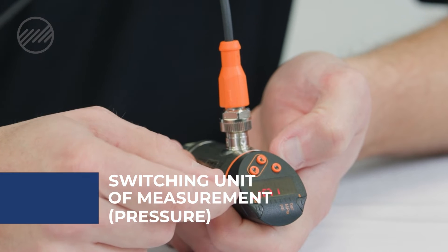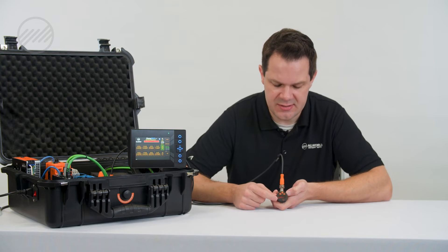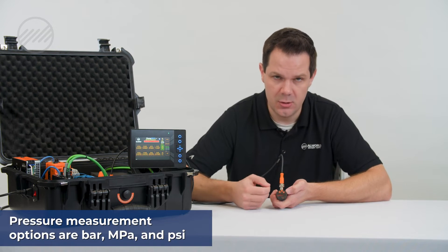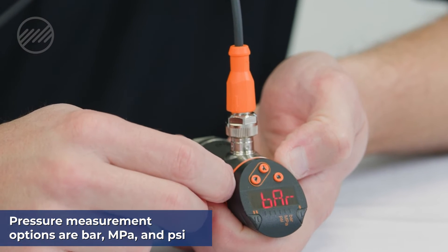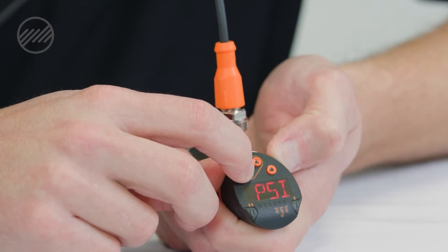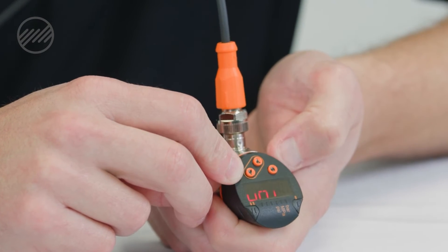Also in this section we have our units of measure. Typically these come out of the box as bar. Your options are bar, megapascal, or PSI. We will change these to PSI. Right now you see the indication is bar — hold my down arrow and it's starting to scroll through my three options: bar, MPa, and PSI. I'm going to select PSI.